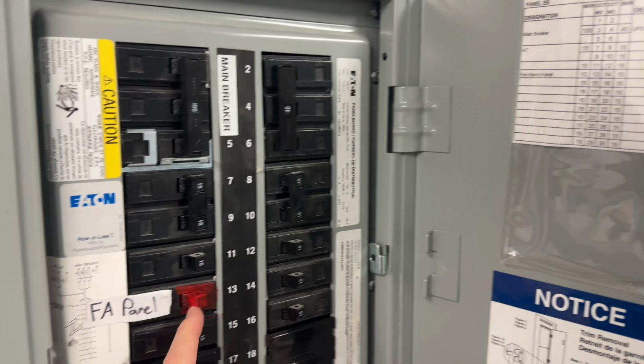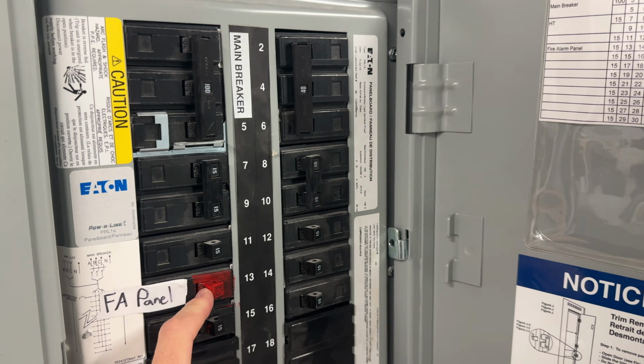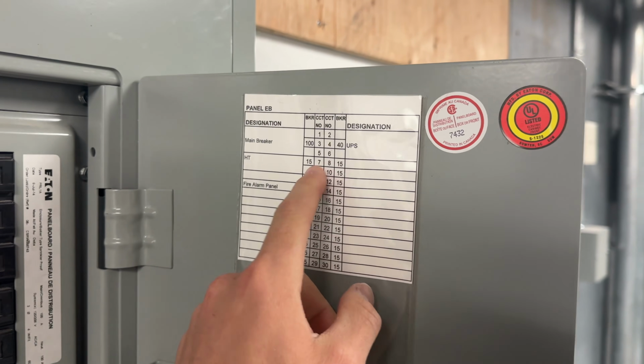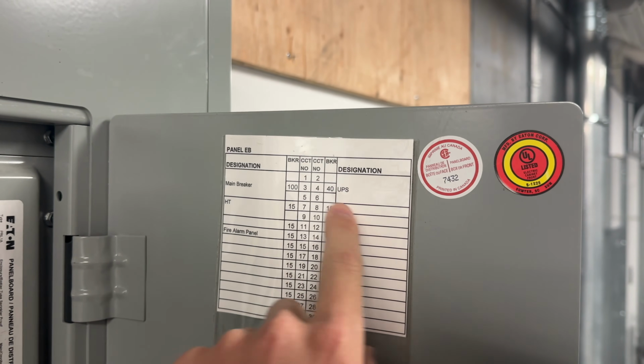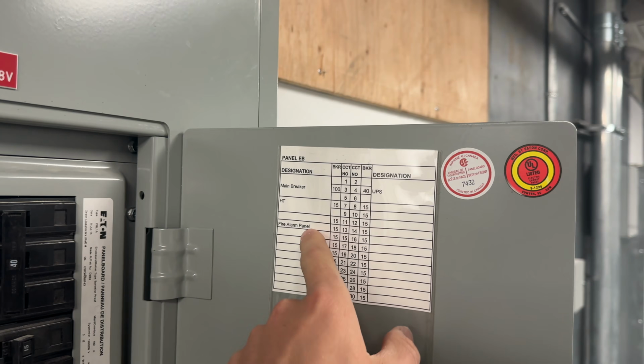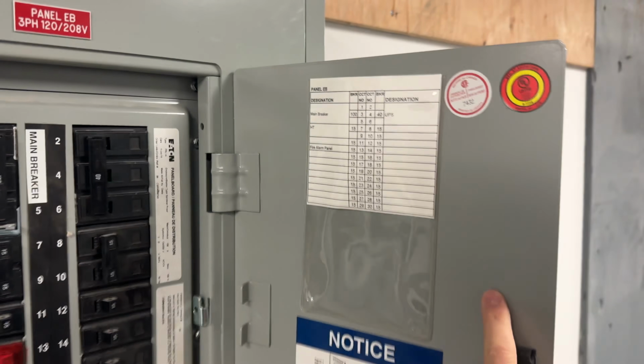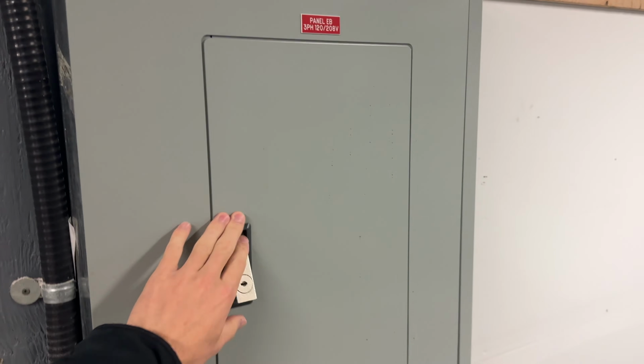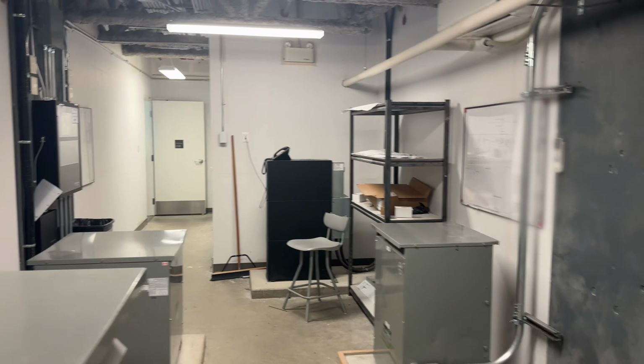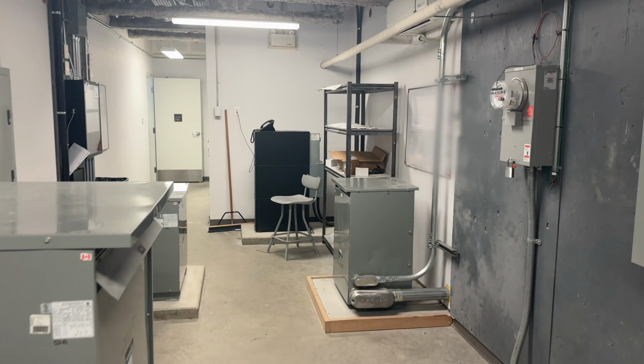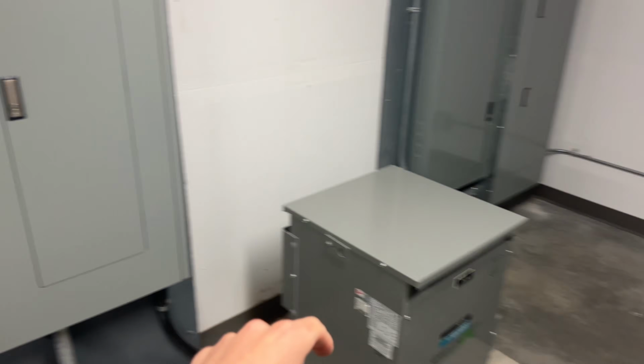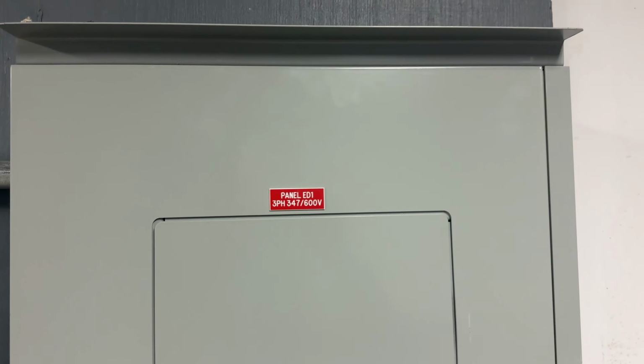And for some reason the fire alarm is on the backup power, but not the main power, not the emergency power. Why that is, I don't know. But you have UPS, fire alarm panel, heat trace, and that's about it for that panel. The other panel, the data panel, is actually on the UPS as well, so that panel will never ever go down. This transformer is providing that. That's one of the 30 kVAs. Here's the other 30 kVA, which is fed from this 347/600 volt.